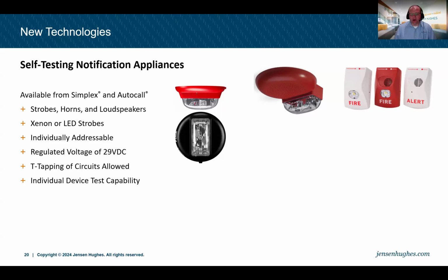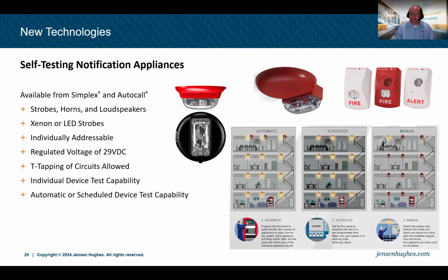And the real benefit is the testing part of it, right? So you can do all kinds of automatic or scheduled device test capability. So you can simply do it in an automatic fashion where you press a button and they all test themselves and you get a report of which ones did not function. You could do it on a scheduled basis, like in the middle of the night when it's very low occupancy, to do your self-testing. And again, getting a report in the morning of all the devices that maybe didn't pass. Or you can actually do it manually. You can do each one individually, put the panel in a test mode, use a magnet on each device, and it'll test each device individually. So really, really neat technology that's been applied to the notification appliance market.